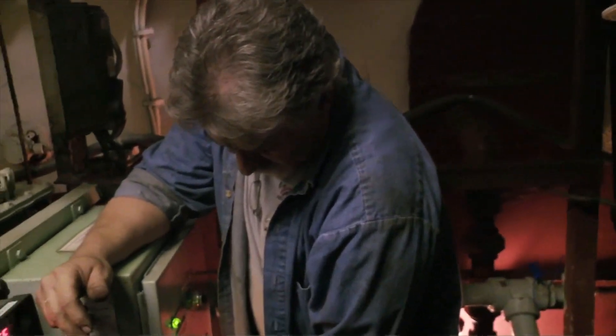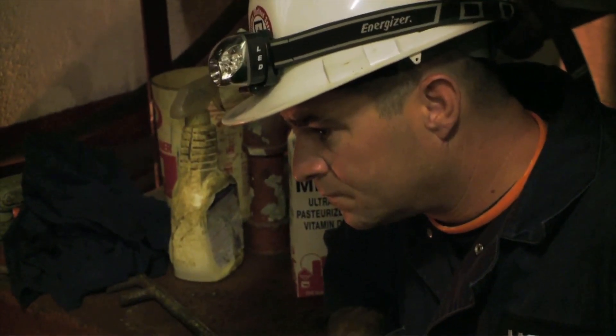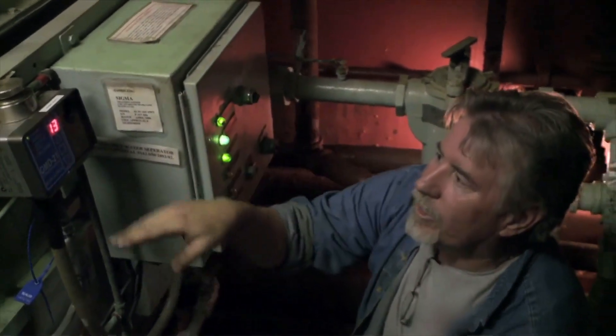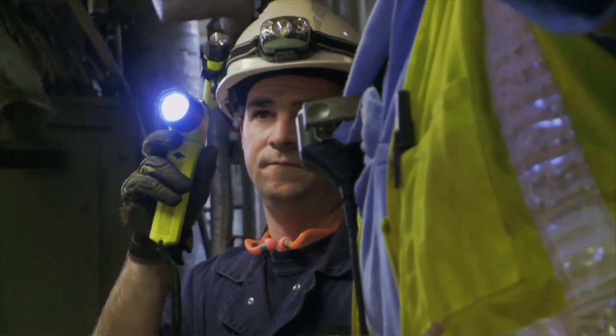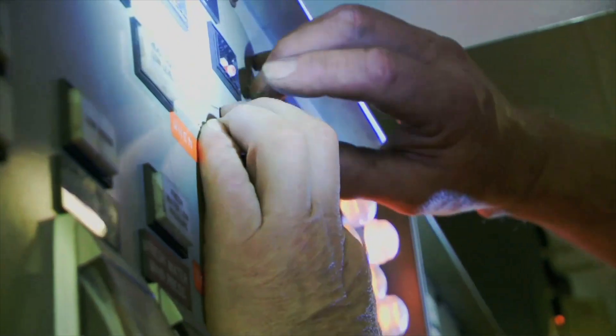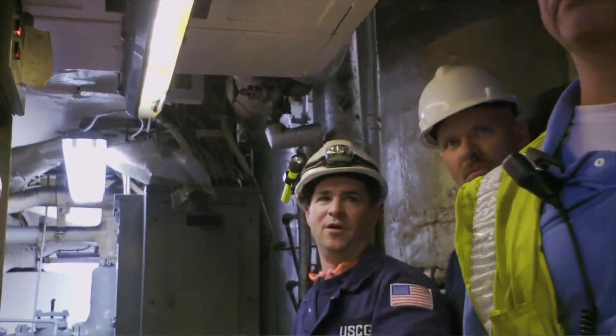They were having a hard time getting that oily water separator going — it wasn't operating the way it should. Other than finding that their equipment was having a hard time getting started, we went to check the alarms and sound system. When it goes above 15 parts per million and shuts down, it gives the operating station an alarm — and the alarm wasn't working properly.